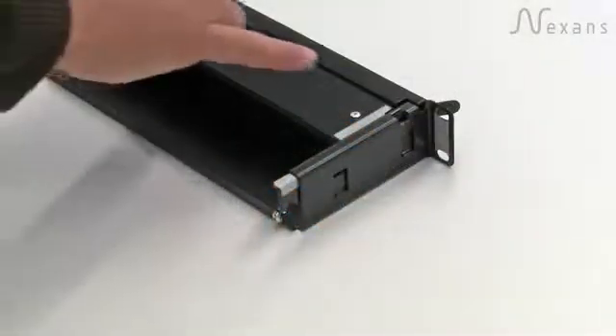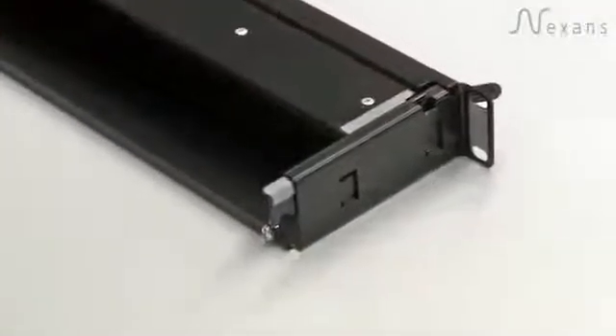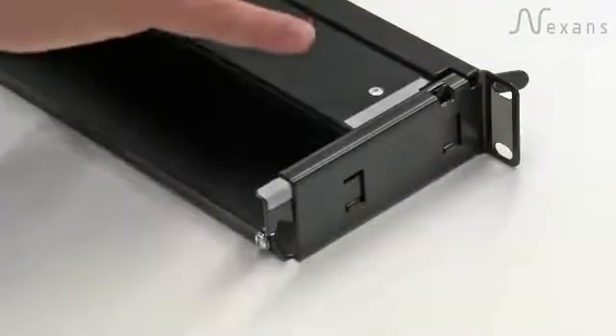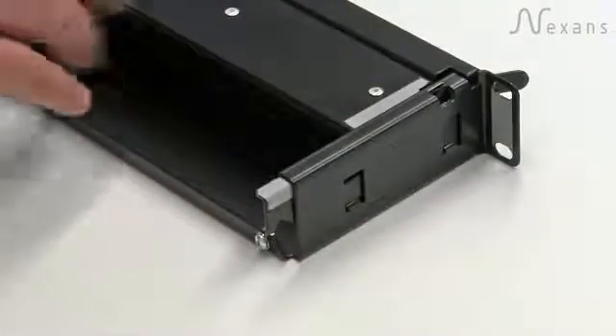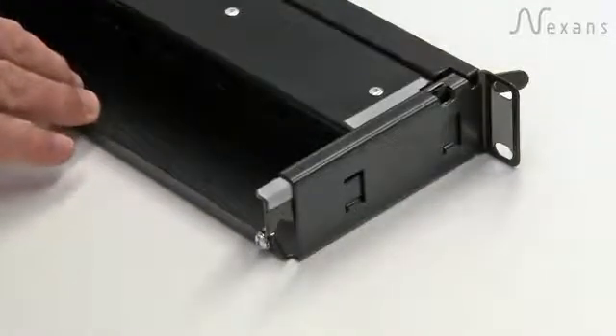One of the key features that has been retained in the new panels is the auto connect feature that allows the panel to be bonded to its rack simply by screwing it into position. You'll notice that here and here we have unpainted features which allow the sliding tray to maintain electrical continuity with the chassis.